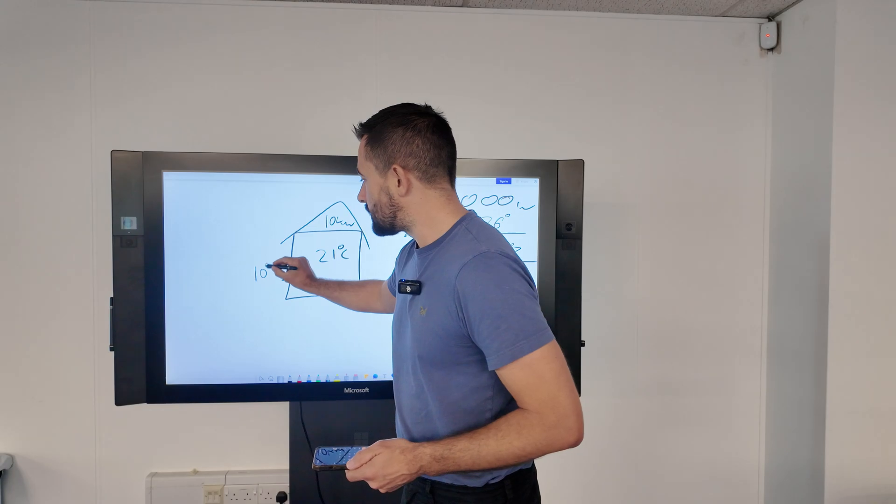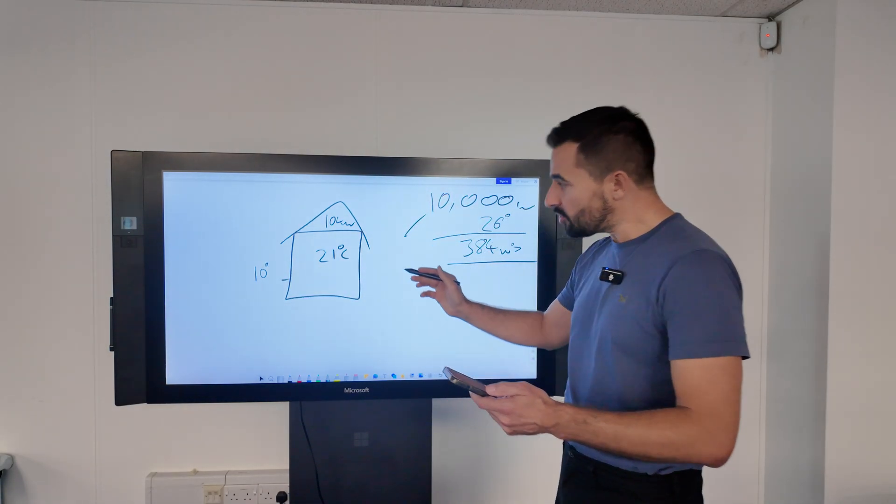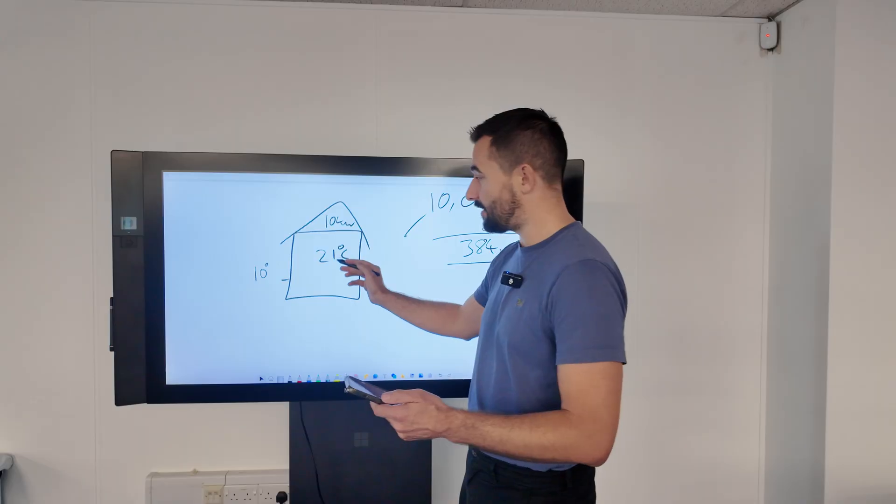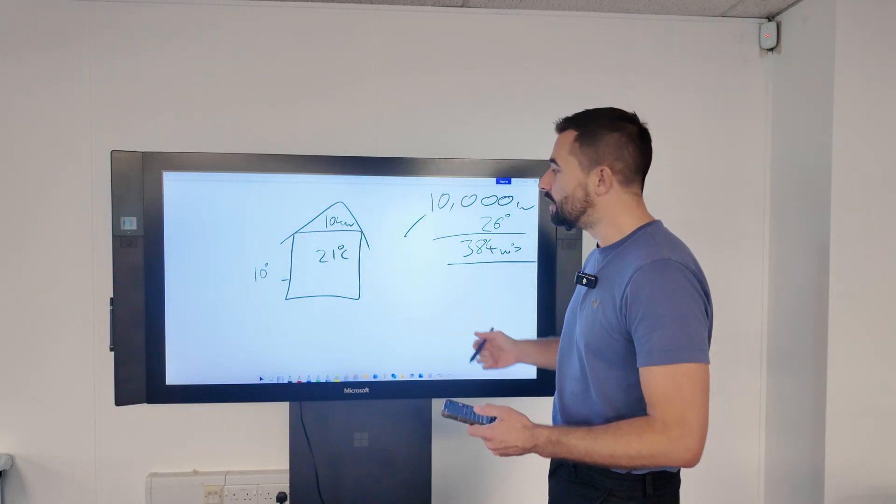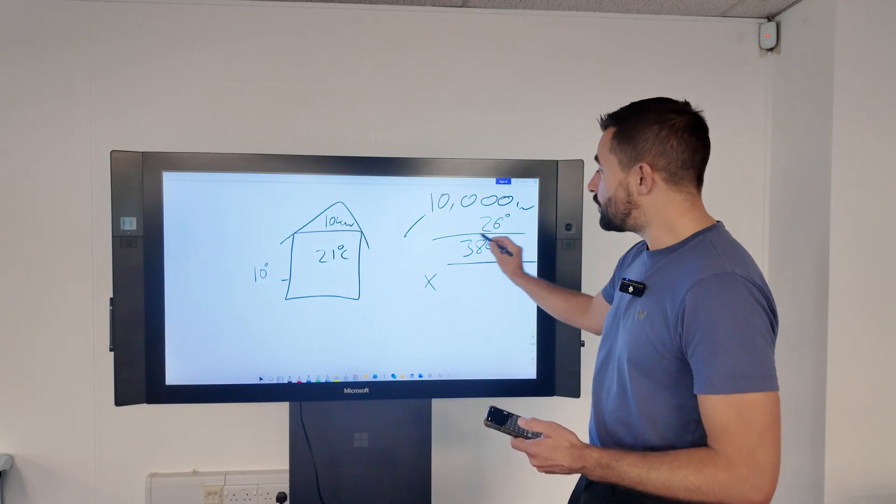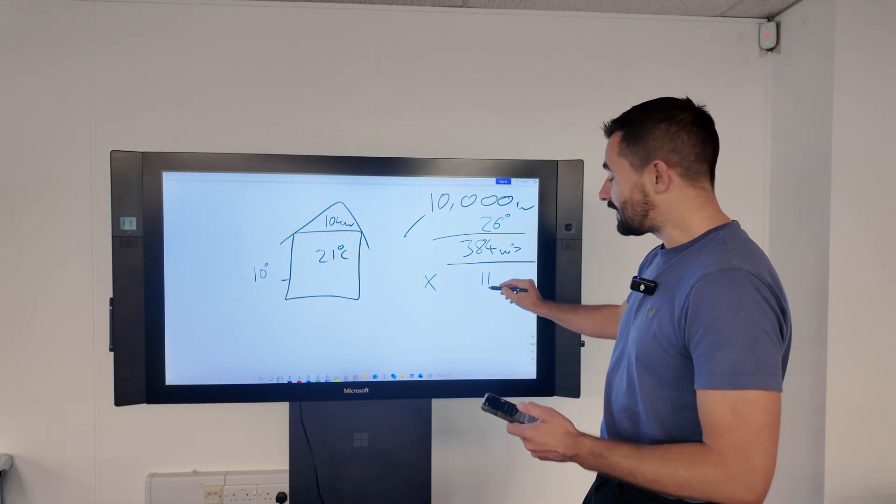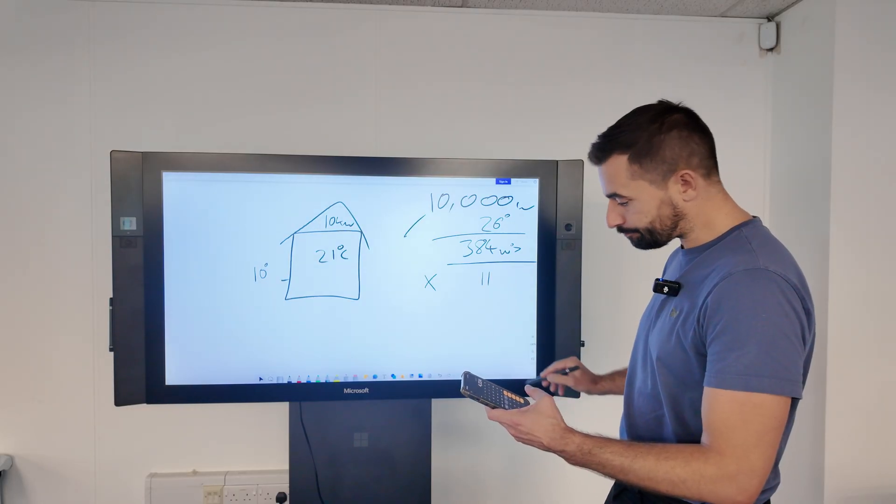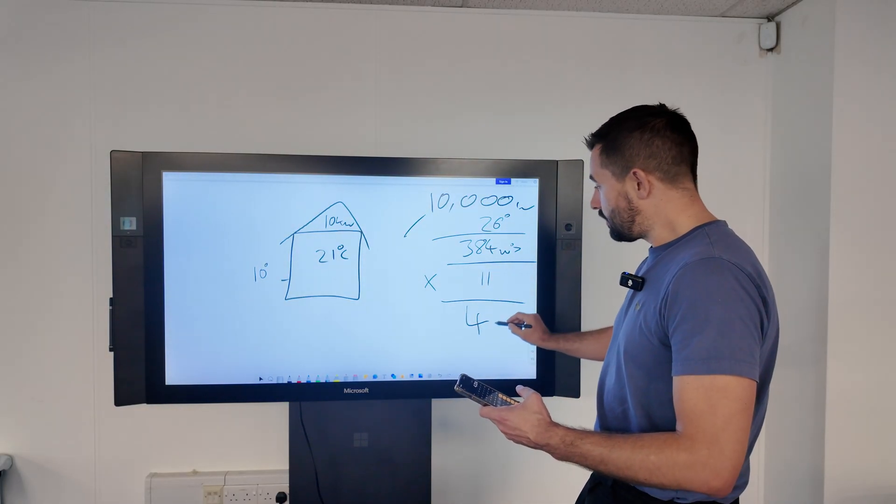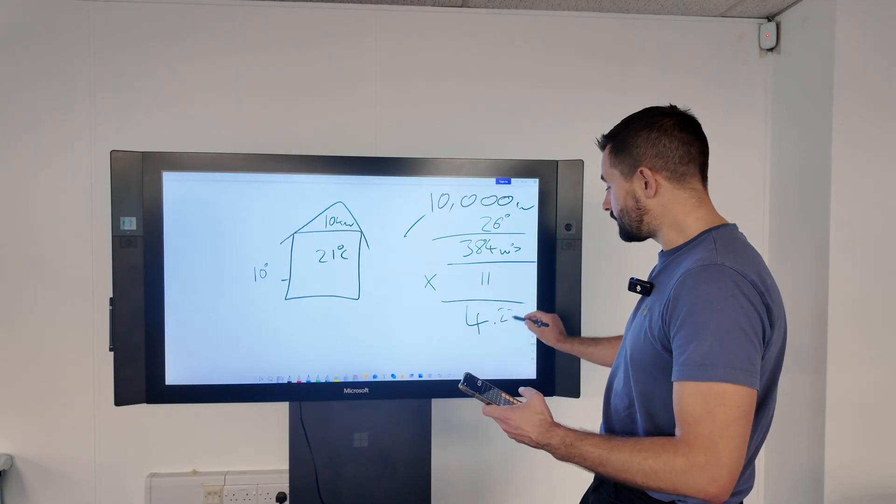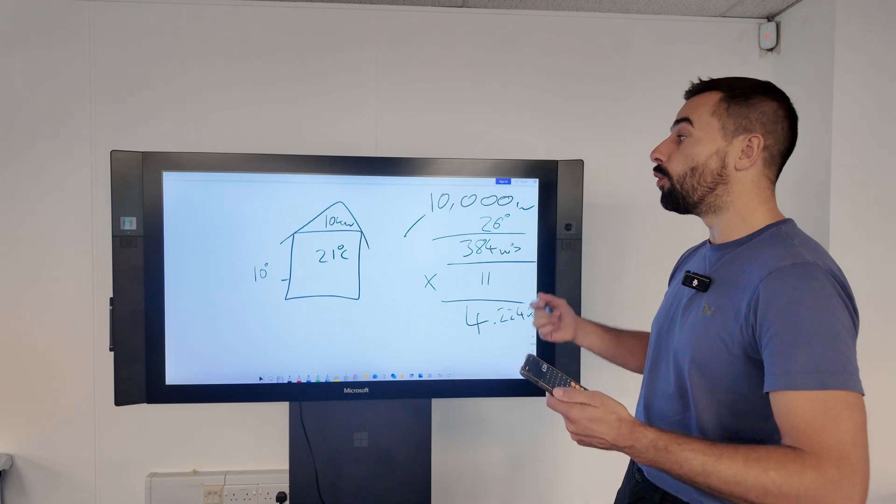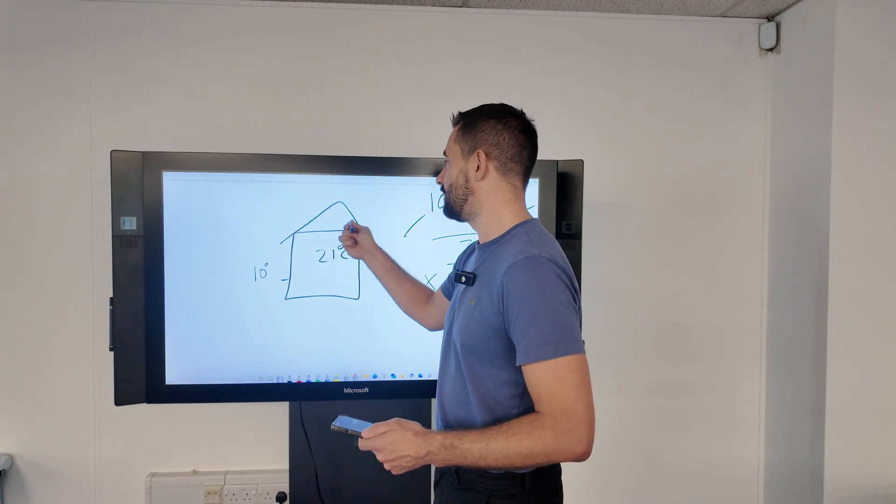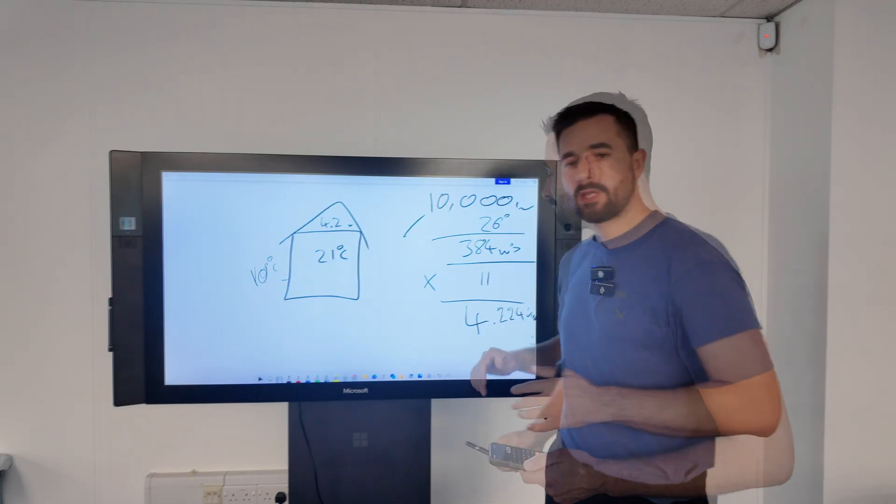When it's 10 degrees outside, let's calculate what our heat loss will be. The difference between that temperature and that temperature is 11 degrees. That's an 11 degree differential. To work out the heat loss, all we do is multiply that watts per degree by 11. 384 by 11. Our heat loss at 10 degrees Celsius will be 4.224 kilowatts or 4,224 watts. Not 10 kilowatts anymore—4.2 kilowatts.